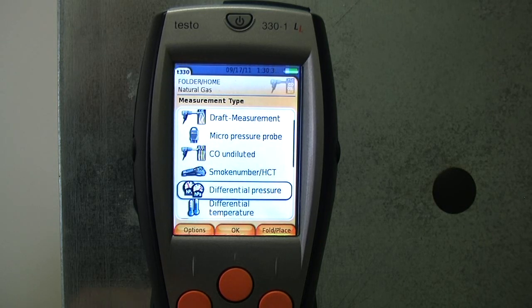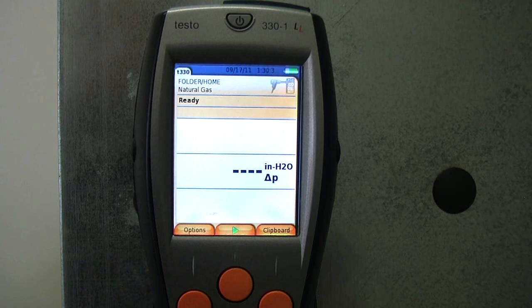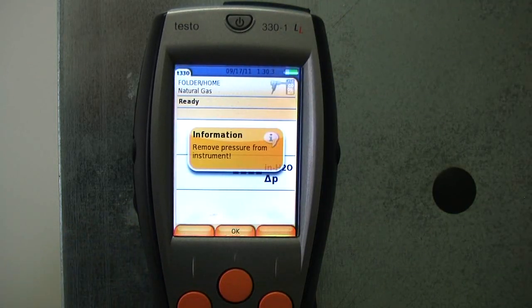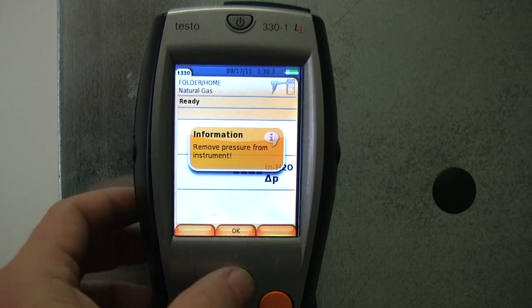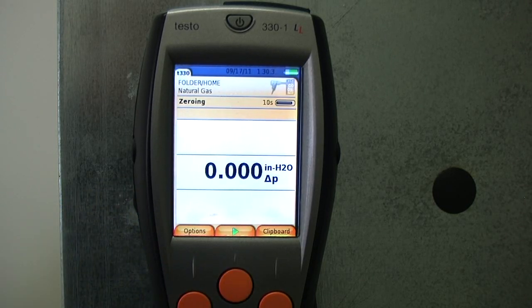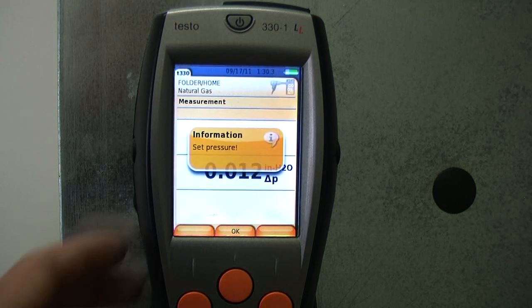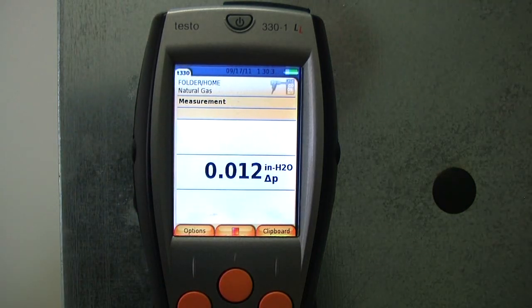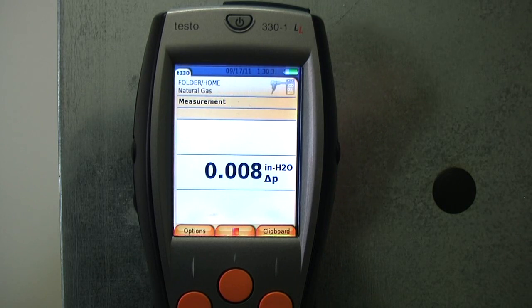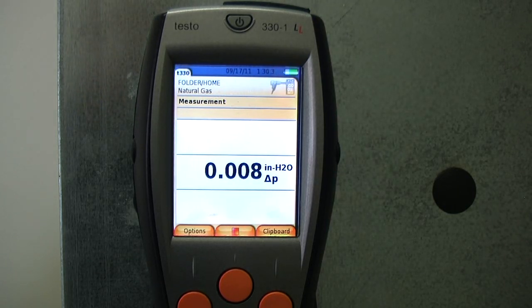So I'm going to go to differential pressure, I'm going to hit OK. I need to unplug my port, let it zero out. OK, it's going to zero out for 11 seconds. This is going to show a negative, that's okay. When it kicks on, it's going to show a negative pressure. Hit OK. I'm going to plug my port back in. Turn my gas valve back on. Wait for the gas to kick back on.